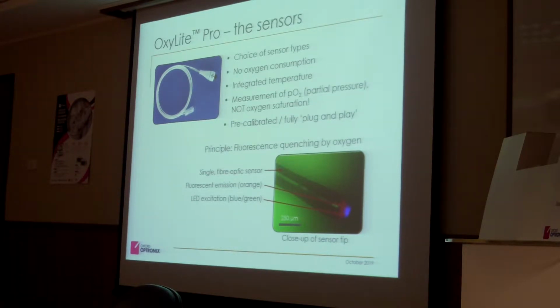And the response time of the sensor is dependent on how fast the oxygen goes into that silicone matrix and out again. Yeah? So we have the glass fiber, we have the silicone matrix, and we have a phosphorescent dye inside the sensor. Inside that silicone matrix, it does not go into the tissue. Yeah? So that's an old picture.